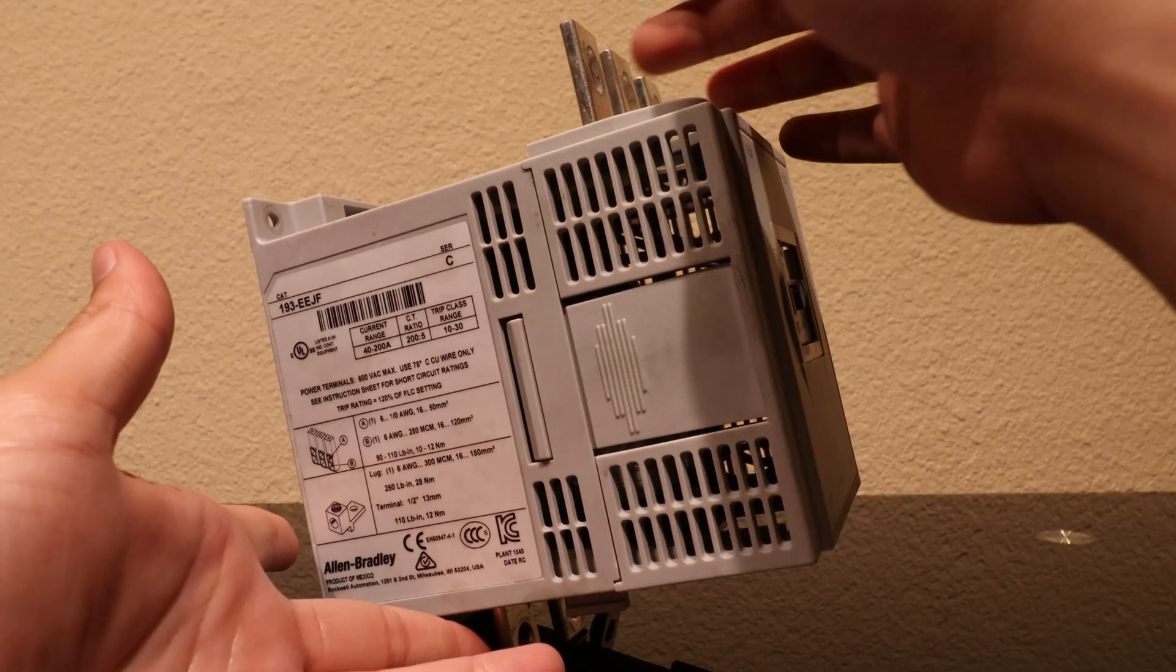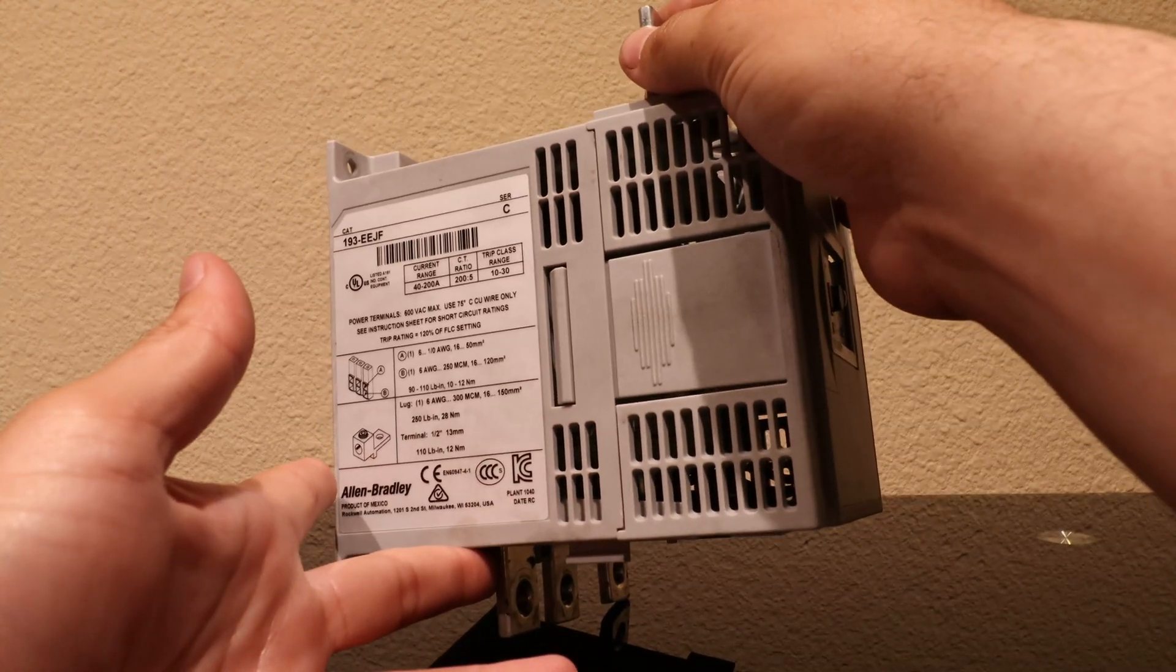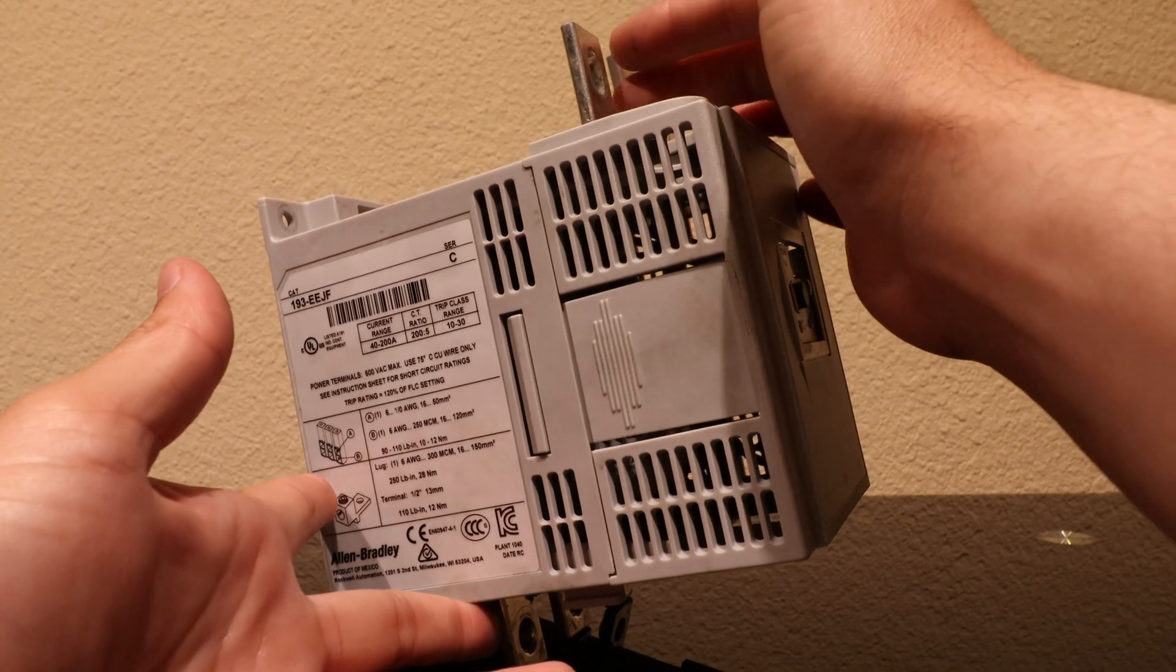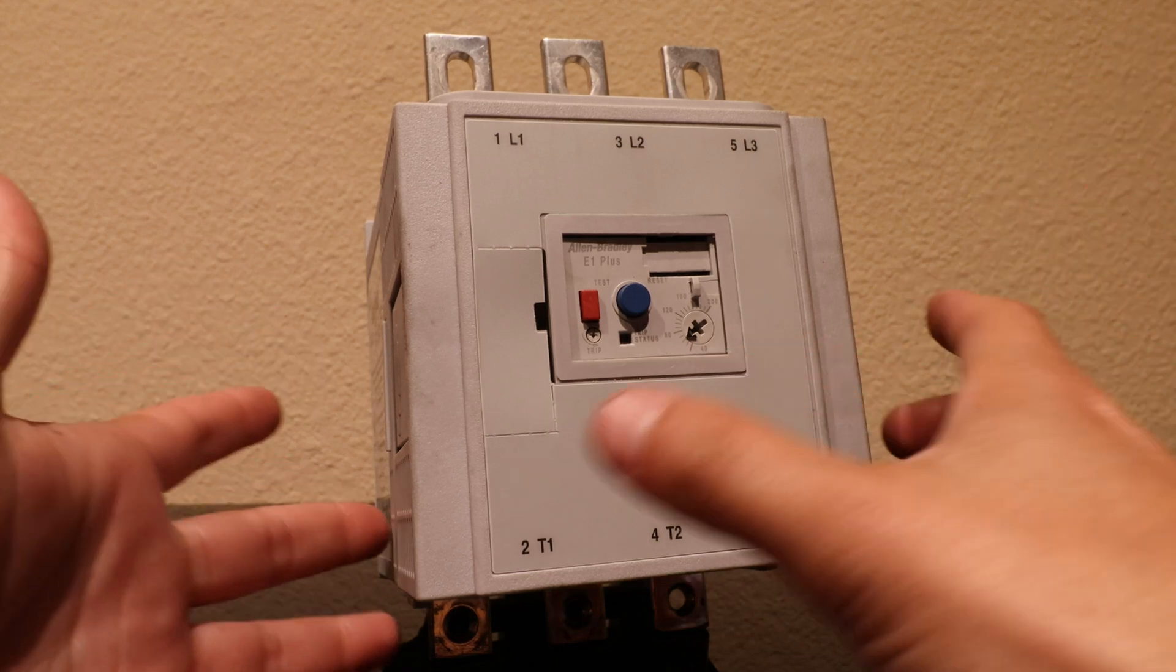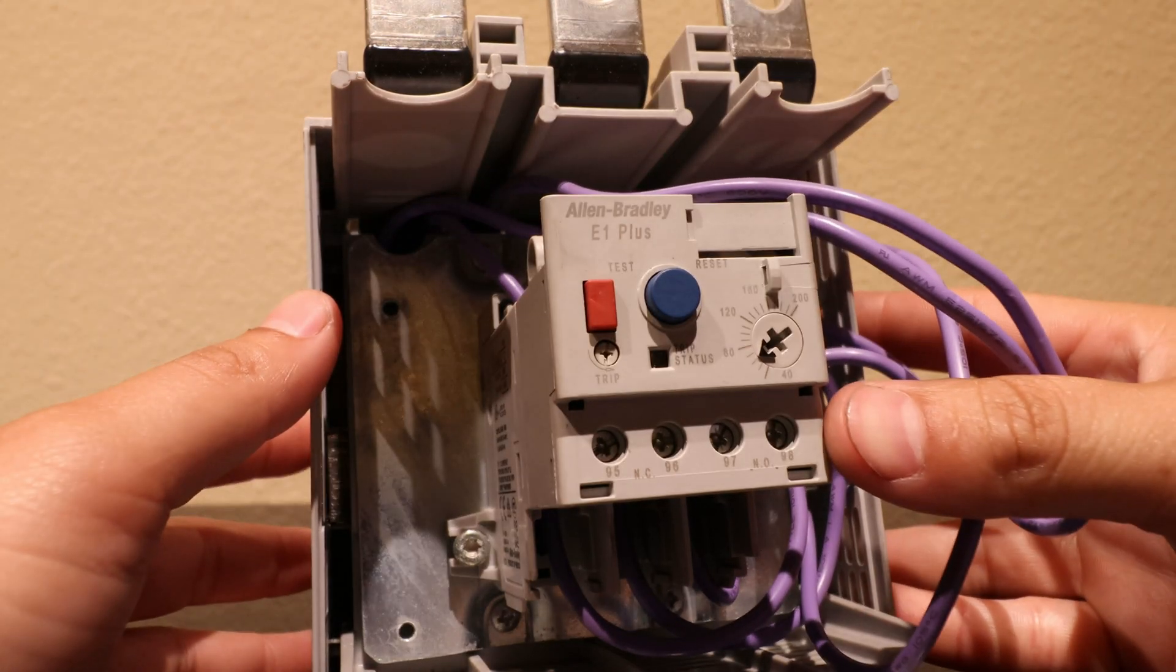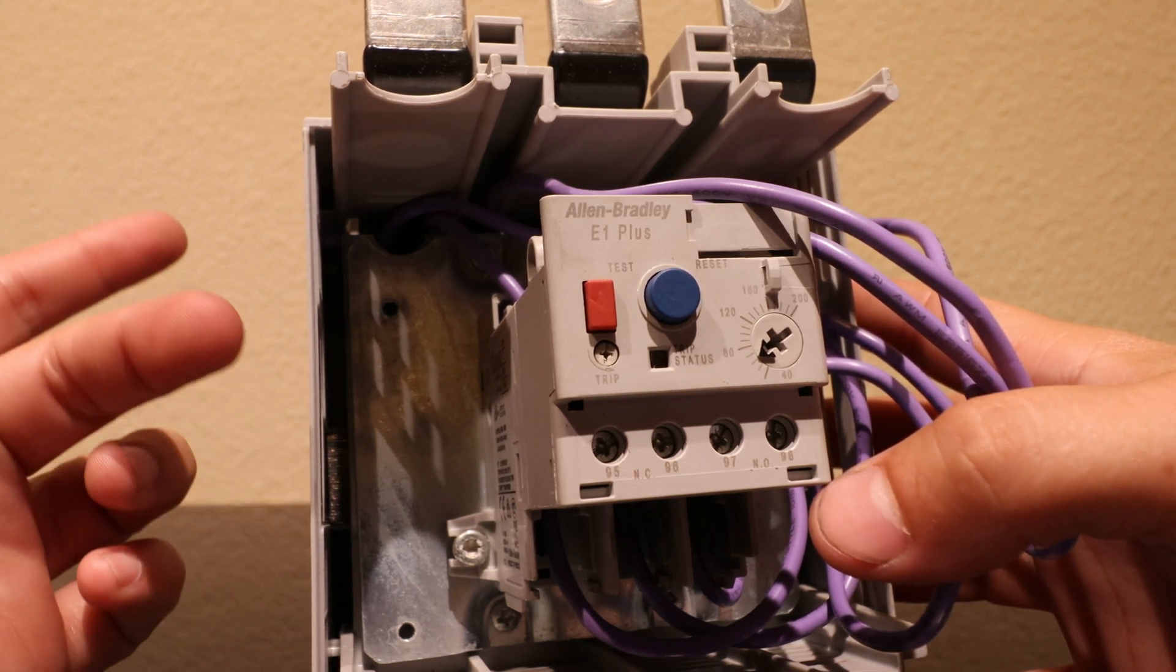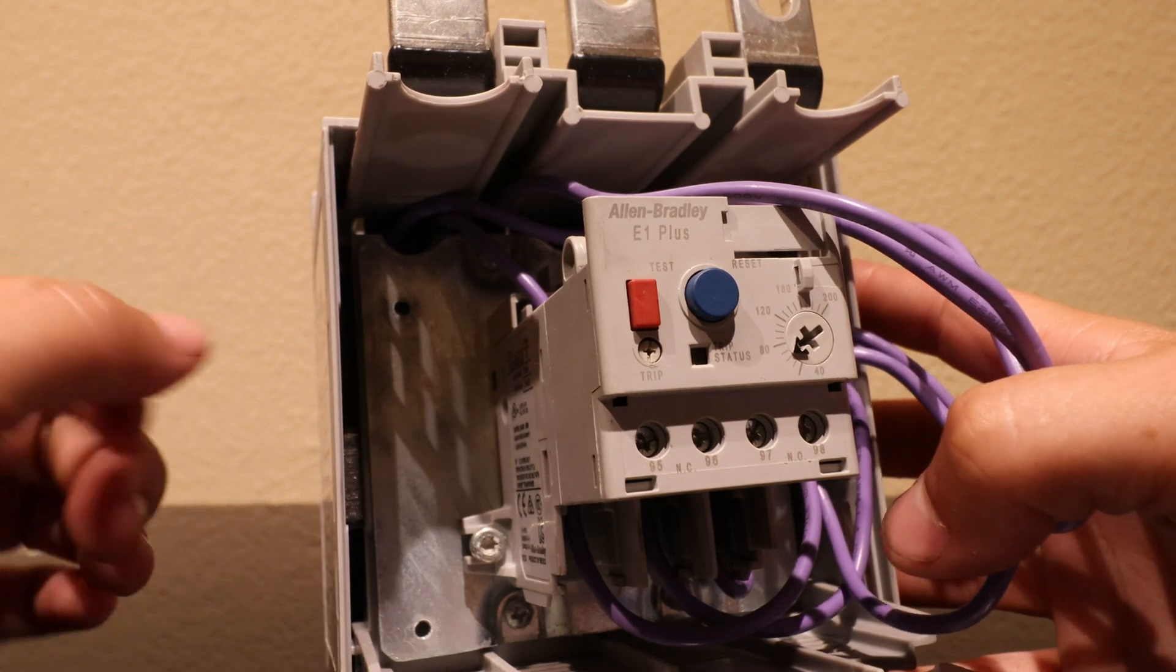Basically how an overload relay functions is they have a bar of metal going through them that is not interrupted by the relay at all. These relays do not cut off current directly to the motor in the three-phase system. These overload relays, when they sense an overload condition, actually open or close the normally open or normally closed contacts right here. By doing so it tells a controller or it actually physically cuts off the contactor to pull out and stop power going to a motor or whatever load this is protecting.